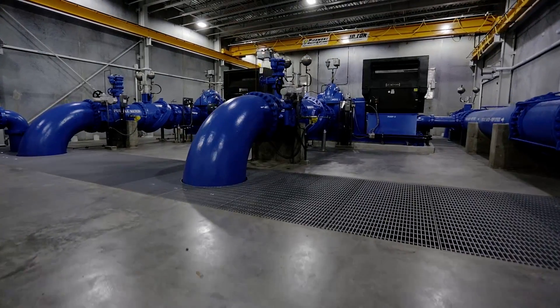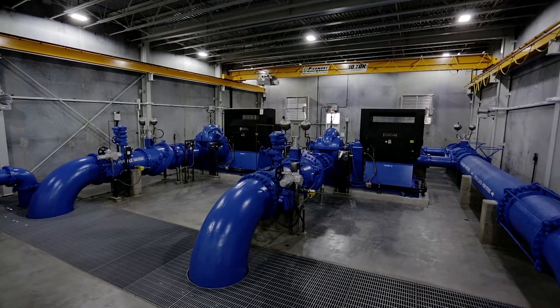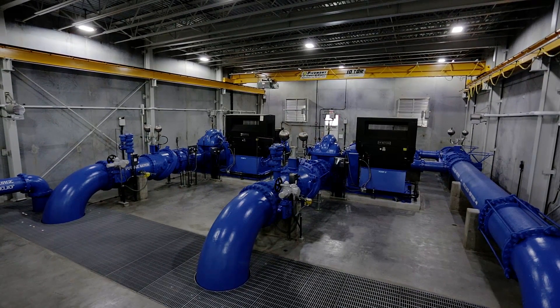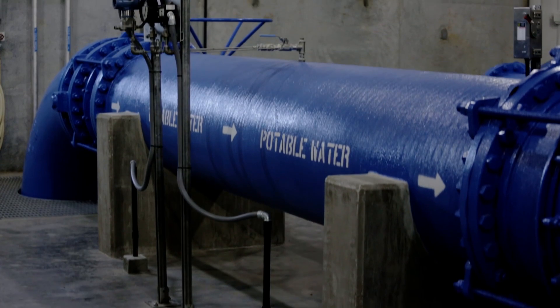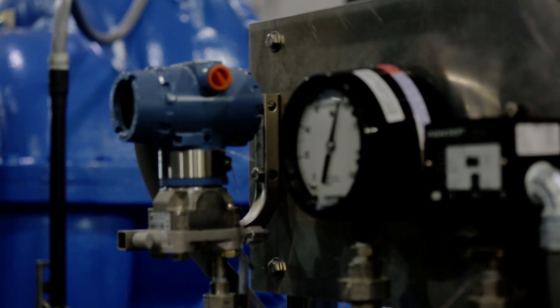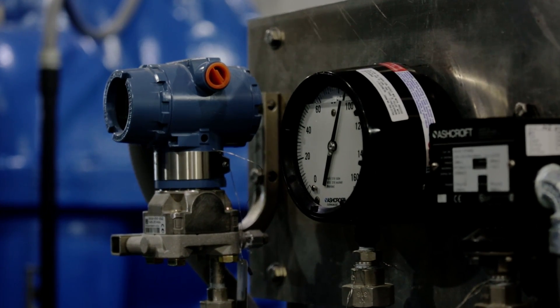Now that the treatment process is complete, the distribution of the water is carried out. The water leaves the plant under pressure generated by electrically powered pumps. A constant pressure of around 80 to 90 PSI is maintained by these initial pumps and pump stations in various places throughout the system.